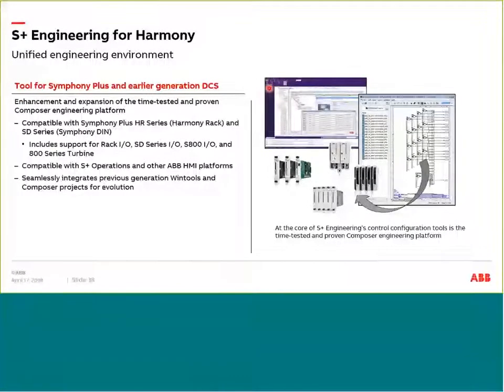When we started this presentation, we mentioned the earlier generation. Many of you are on MFCs, MFPs, BRC 100, or you're already on S+, where you have BRC 400s and 410s, or maybe you even have our DIN products, the SPC 700 or the HPC 800. All these can be configured in S+ engineering. We have done this with many of our users who have the legacy EWS or Composer: we can take the EBP file, which is the project file, come into S+ engineering and upgrade the database so that it's compatible with S+ engineering.